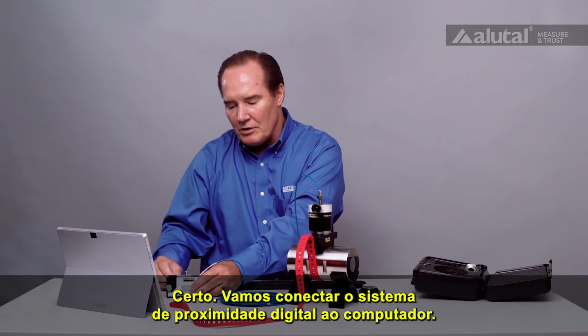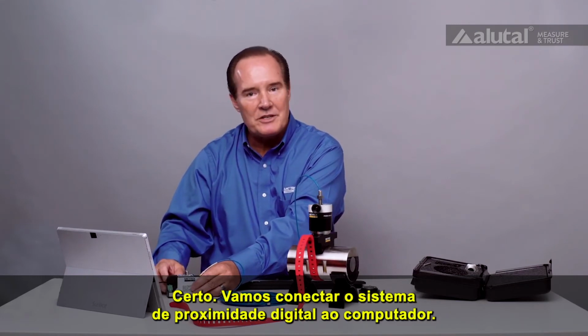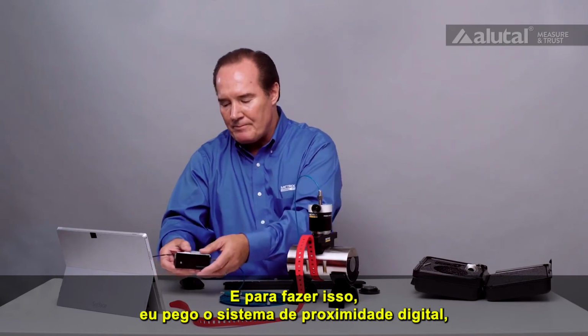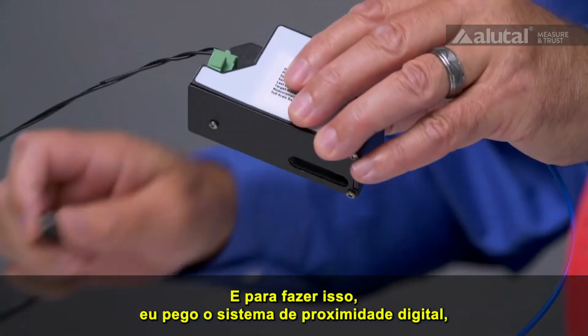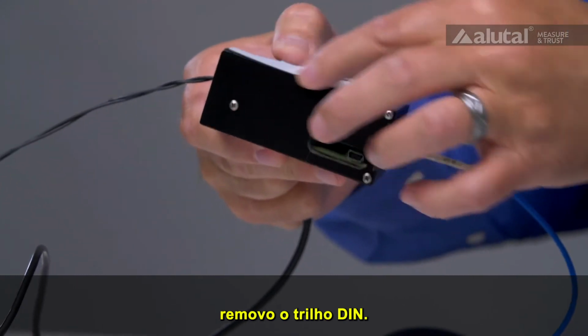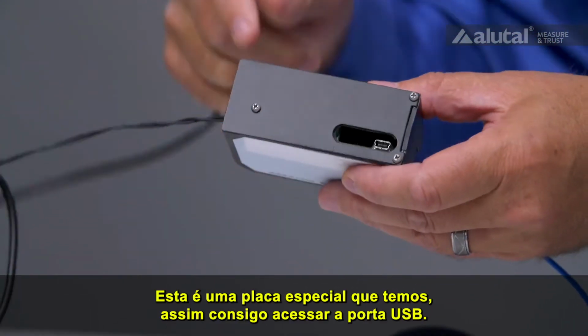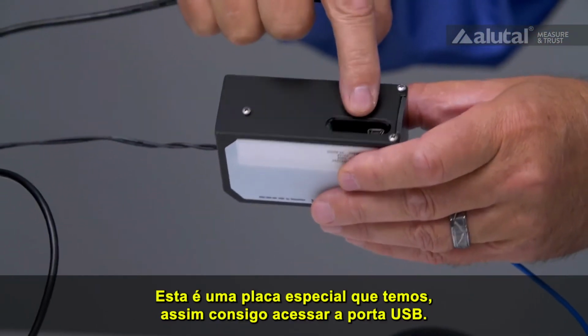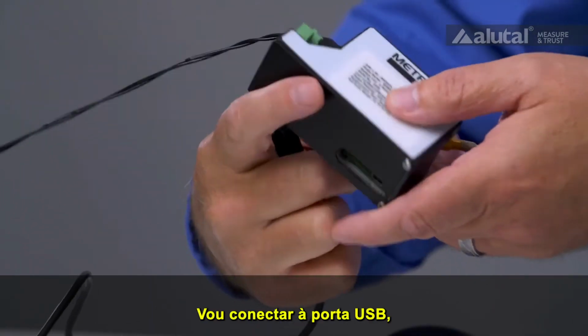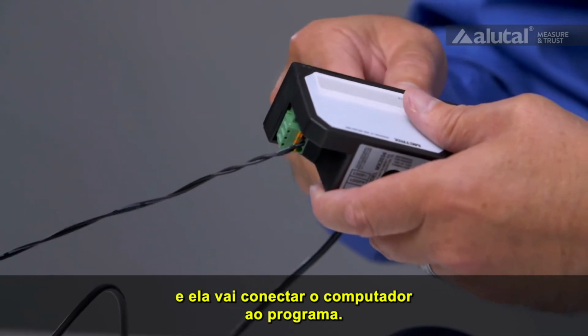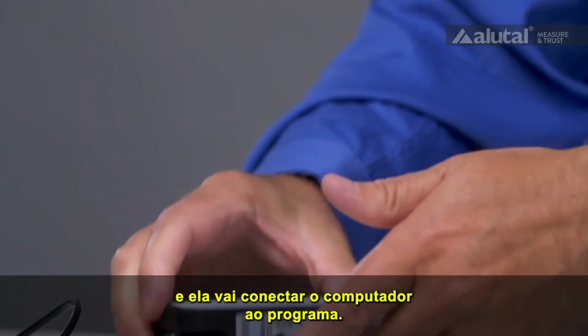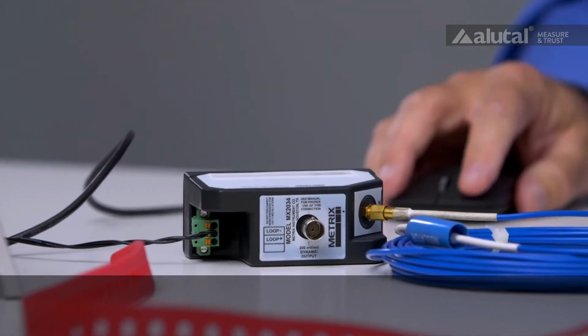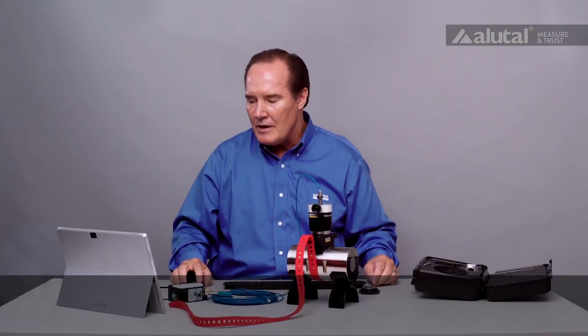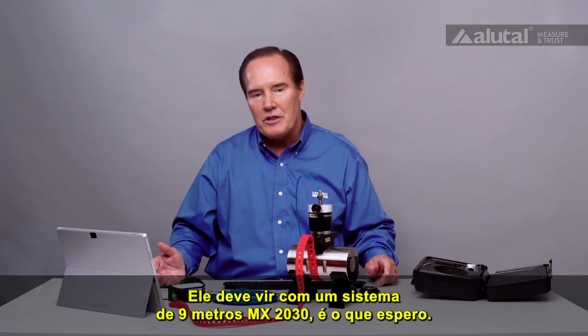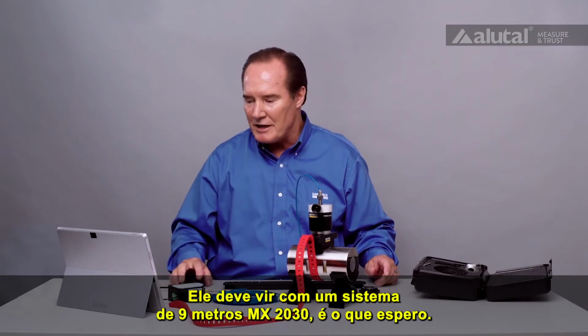All right, so let's go ahead and plug in the digital proximity system to the computer. To do that, I take the digital proximity system and remove the DIN rail cover or mounting. This is a special plate we have on so I can access this USB port. So I'll go ahead and connect to that USB port, and that basically connects the computer to the software. And I can hear my connection. I'll go ahead and start the software now, and it should come up with an MX2030 9-meter system, and that's what I'm expecting.